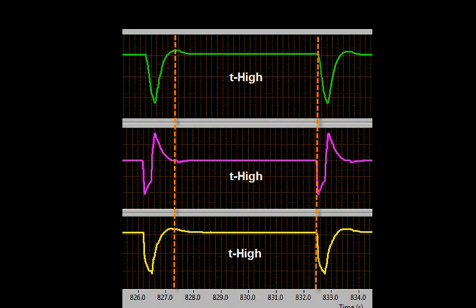Next, T-High. T-High is the set time for the upper CPAP level, or the P-High phase. The T-High setting allows for sustained recruitment, enabling improved gas exchange by increasing alveolar surface area.